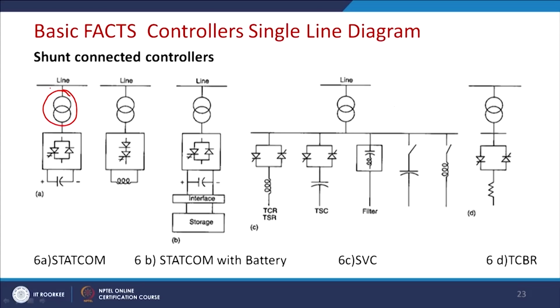And when we use a voltage source inverter, then we use this kind of topology followed by a DC link capacitor. If we use a current source inverter, generally we use an inductor. A current source requires a high value of inductor, and for this reason the voltage source solution is cheaper and effective. In most applications we find that STATCOM is operated by a voltage source inverter. Whether voltage source or current source inverter, if it carries a storage device like distributed generation such as a solar cell or battery, then it can also inject active power into the system. Then it will be a FACTS device with storage, and this is the STATCOM with the battery.